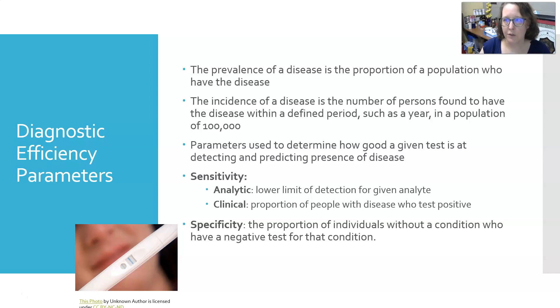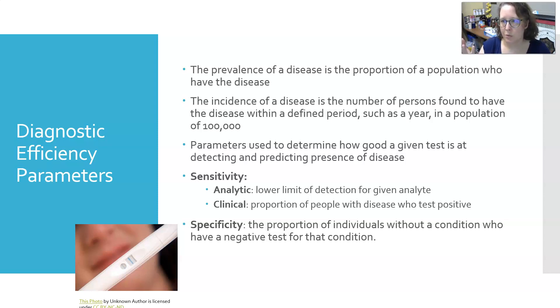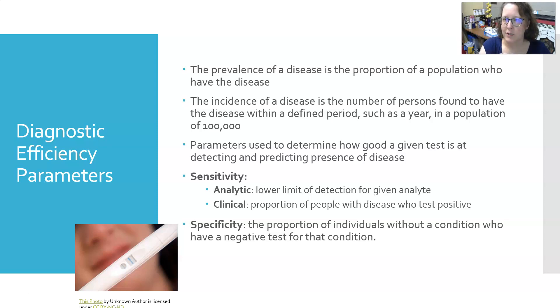There are two types of sensitivity often referred to in the lab: analytical and clinical. Analytic sensitivity is the lower limit of detection for a given analyte — for example, whether it can detect down to zero, 0.5, or 10 units. Anything below that lower limit would have to be reported as less than that value for the given analyte.